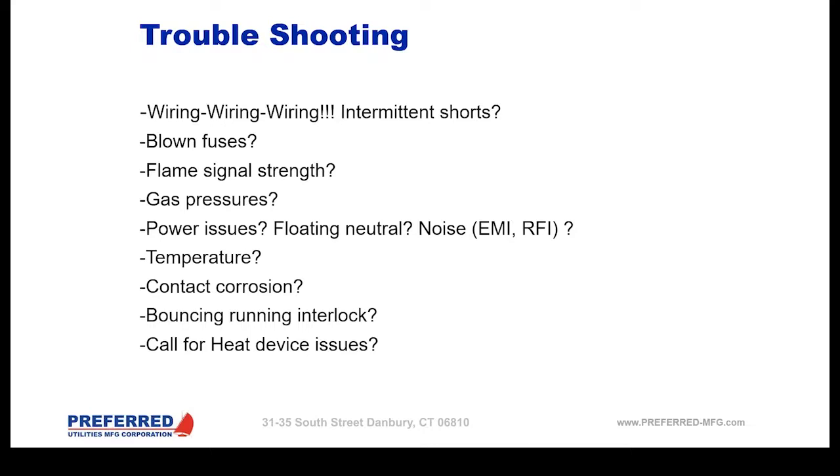Gas pressures, has something changed there? That could cause issues with the light off, could cause issues with making rate. So gas pressures need to be looked at.